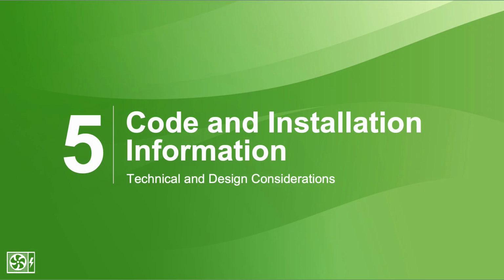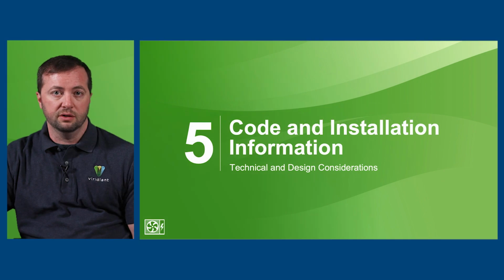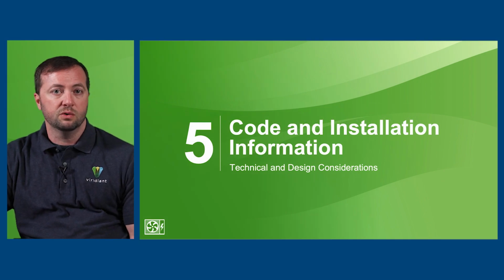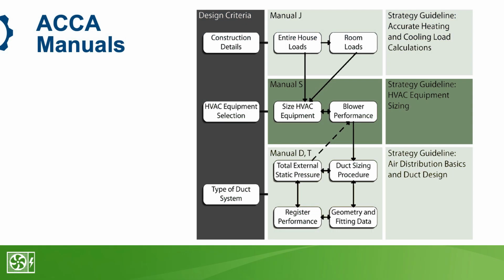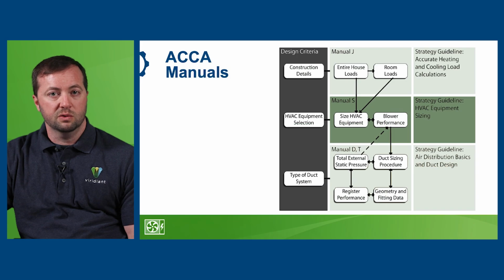Code requires that all HVAC systems, including heat pumps, are designed and installed in accordance with industry standards for calculating the sizing, equipment choice, and duct layout. Here we see a diagram showing the 4 key manuals from ACCA, the Air Conditioning Contractors of America. The manuals are books that software packages are then built off of that get into all of the engineering details such as heat movement, airflow, solar gain, etc., to precisely calculate the home's heating and cooling demand, select equipment based off of that, and then create a duct layout that's best going to help the home meet those loads.